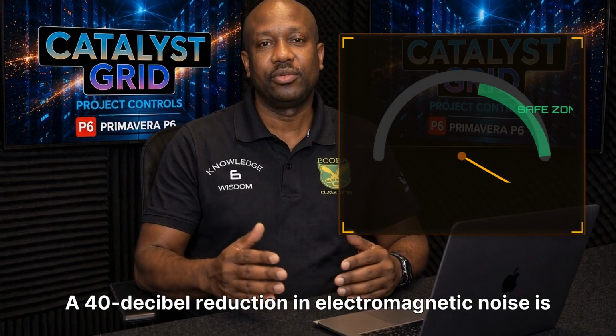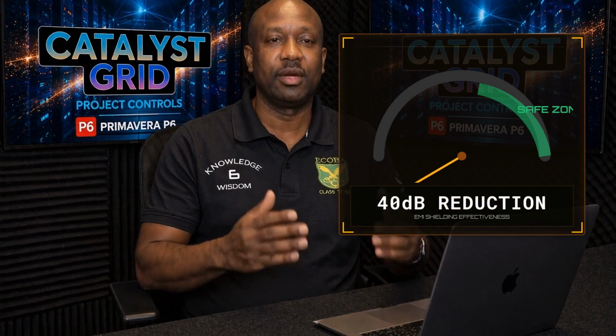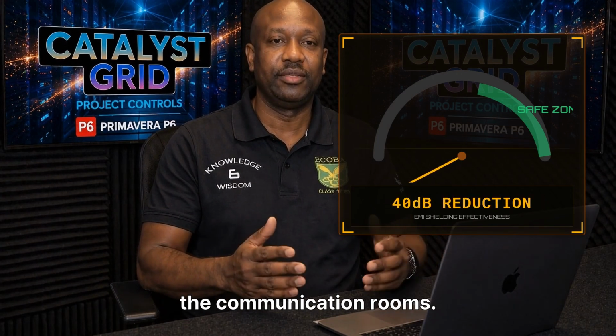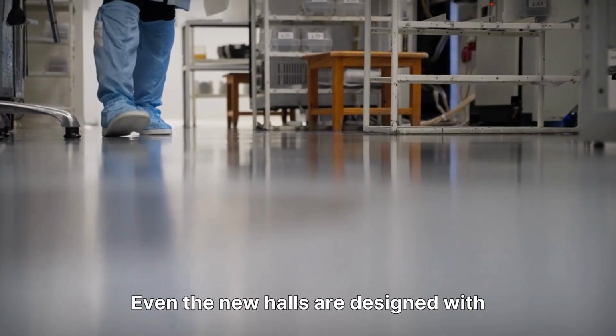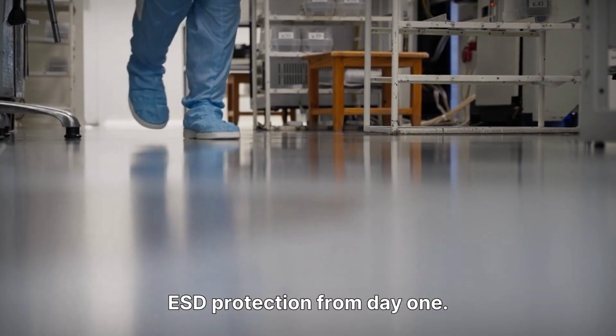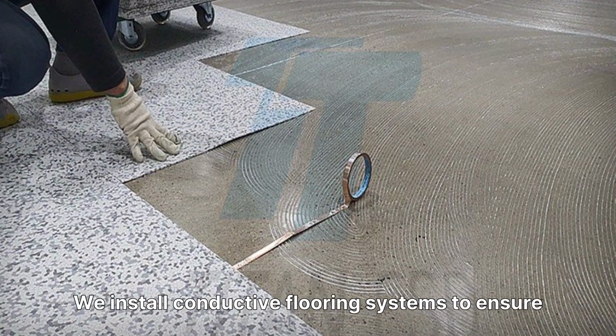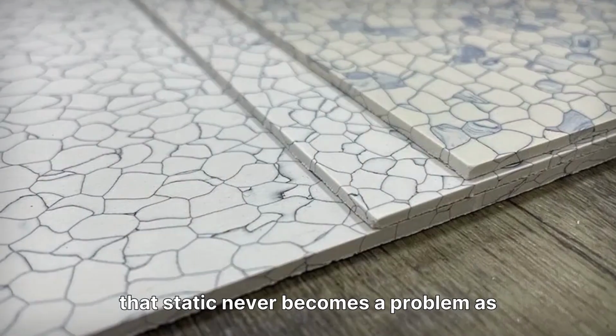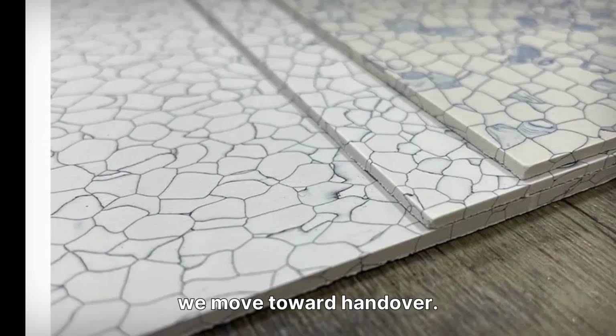A 40 decibel reduction in electromagnetic noise is our baseline for any high-energy work near the communication rooms. Even the new halls are designed with ESD protection from day one. We install conductive flooring systems to ensure that static never becomes a problem as we move toward handover.